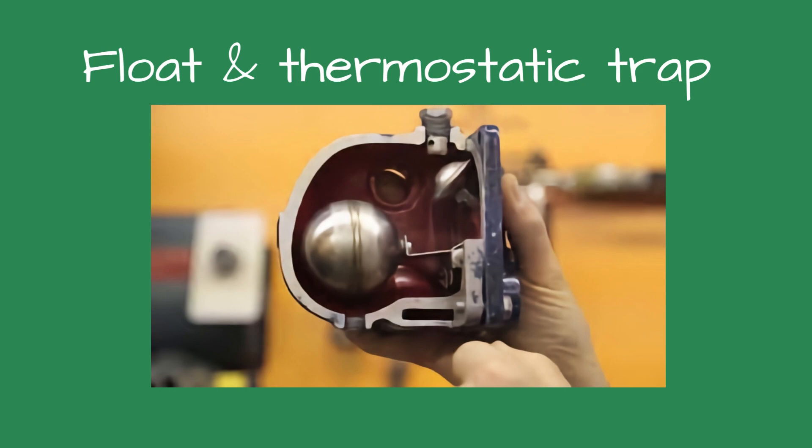Steam trap life. According to schoolfacilities.com, the average life of a thermostatic steam trap element is about three years, and about six years for a float mechanism in a steam trap. When replacing a steam boiler, I like to replace or rebuild the steam traps in the building. We did this for a large apartment building in my area, and the owner told us their fuel costs dropped dramatically.